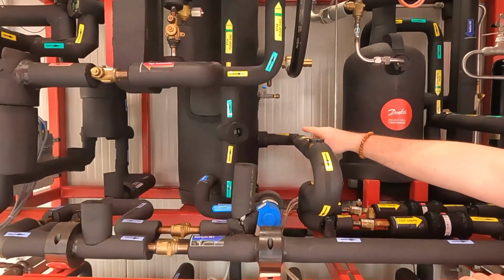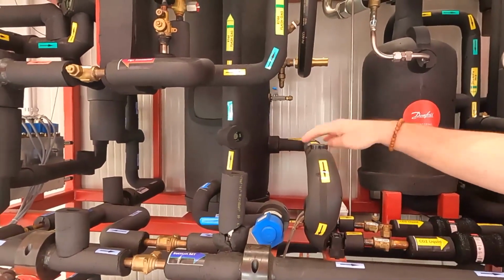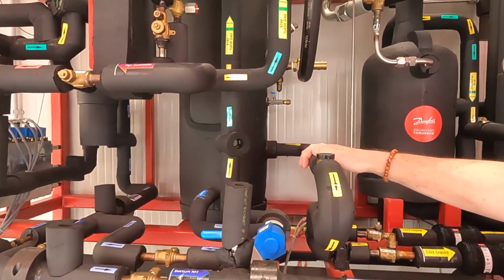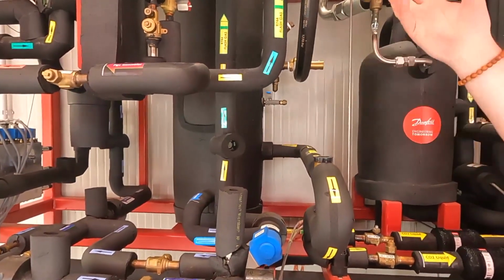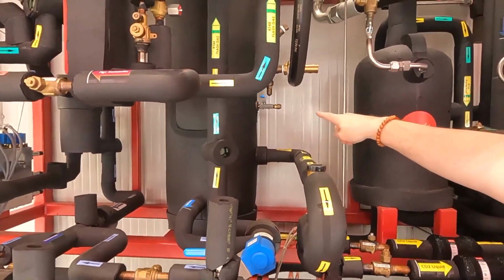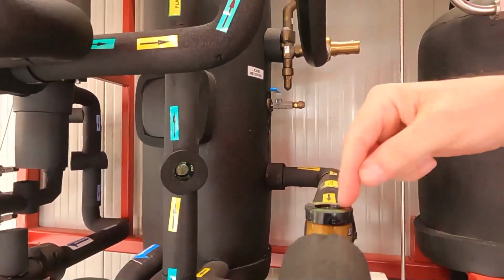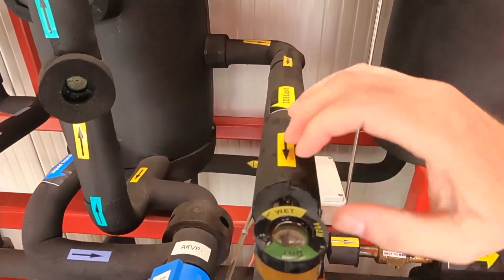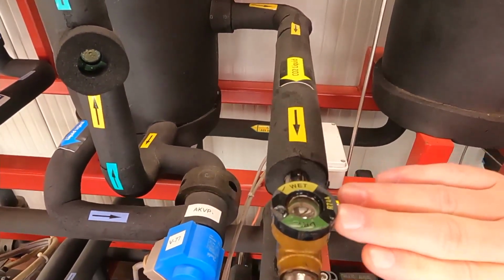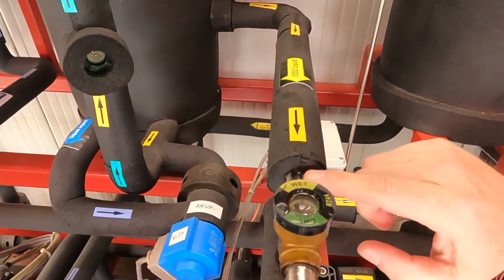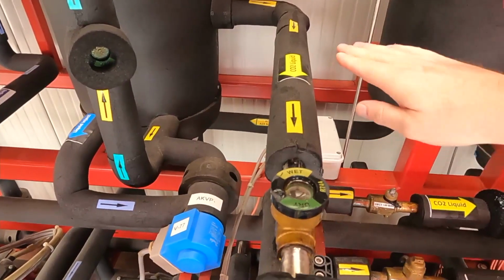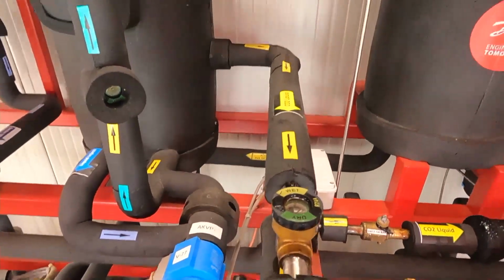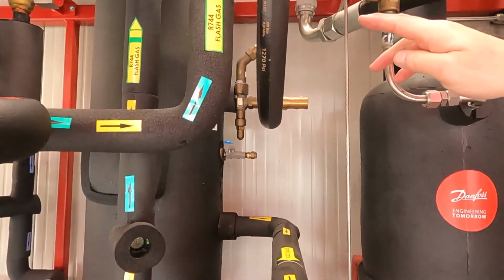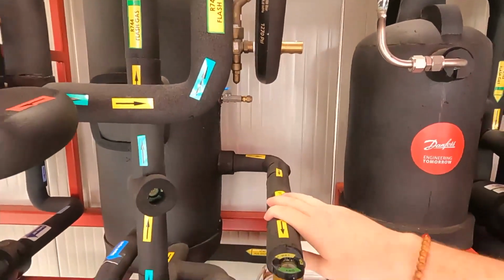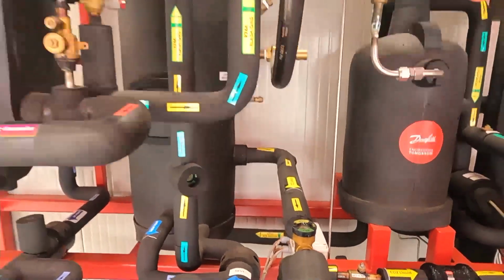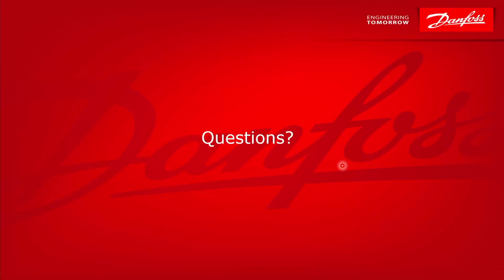So here, this only gets charged up until it's above this line. So when I charge this particular system, when I come meet it at various training sites, I literally do what I said earlier. I'll make sure it's above 100 pounds with vapor. Then I will connect to this port here and start charging with liquid. And then I just look in the sight glass here, if you can look in there, and you kind of see a little river. I don't charge it all the way up because I want it to have some turbulence where I can see that I'm at the very top of this line, which is how I simulate being above the bottom sight glass. So the balance of the flash tank from that point up will just be vapor, if that answers your question. So this one's probably charged to about 30% to get it above the bottom sight glass. I hope that answered your question.